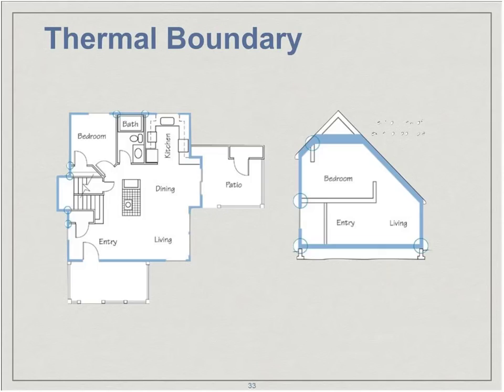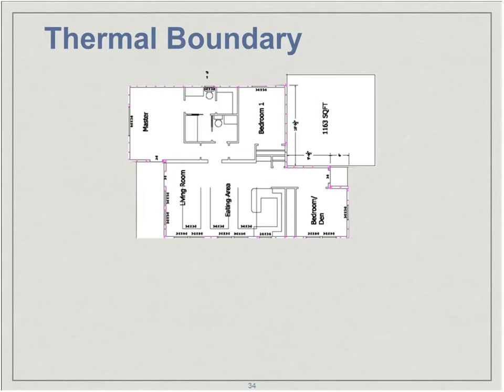Never forget what's inside and what's outside of the building. Unfortunately, a ventilated attic space is outside, and a ventilated crawl space is outside. Most garages are outside the building, and yet this is where conventionally people put their heating and cooling systems. We don't want to do that—we need to bring the heating and cooling systems within the thermal boundary as much as possible. That'll make a big difference: probably 20 to 30% savings just by pulling the mechanical system inside. We'll talk more about this in a minute.